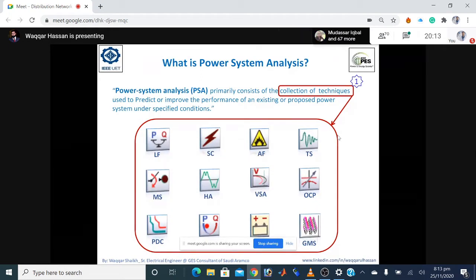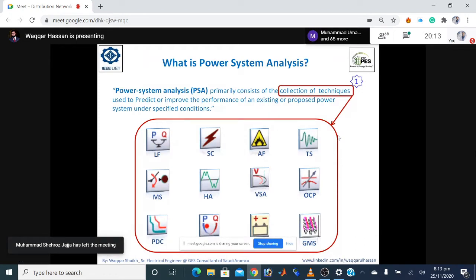This study also helps generate work permits before starting electrical work on energized equipment. Other types of studies include transient stability study, motor starting dynamic and static acceleration study, harmonics analysis, voltage stability analysis, and optimal capacitor placement study, also called power factor correction study. One of the most important studies with respect to plant commissioning is protection device coordination study. Similarly, there's optimal power flow study, DC system analysis study, and grounding mesh studies. All these are different types of analysis referred to in this definition as collection of techniques.